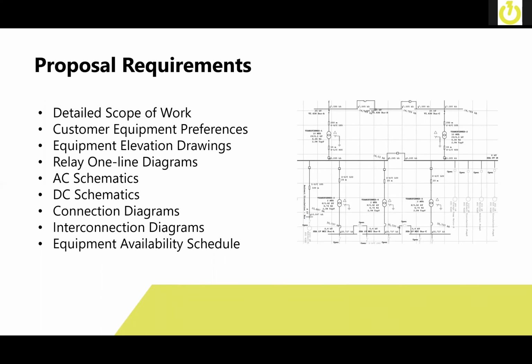So we want to make sure whenever we do the proposal that we have enough space to be able to mount the new equipment. We also like to see the relay one-line diagrams, just to make sure that we're optimizing your system and recommending the correct protection. AC schematics, DC schematics, to get an idea of what type of part number we would need to use and how many test switches we would need to use. What type of control schemes might need to be taken out during the installation and demolition process.